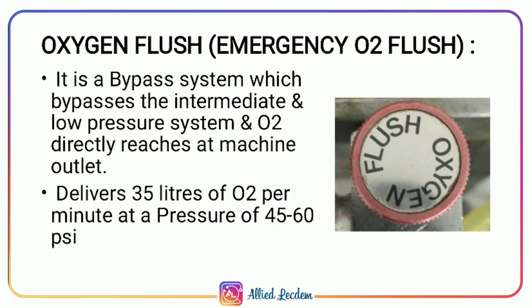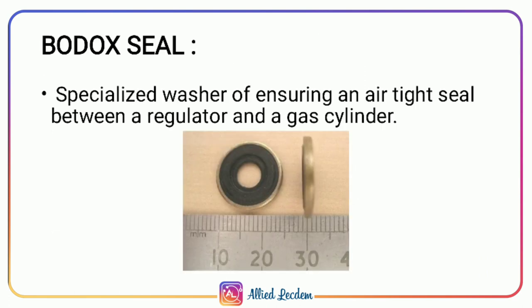The oxygen flush is an emergency bypass system which bypasses the intermediate and low pressure systems so that oxygen directly reaches the machine outlet. It delivers 35 liters of oxygen per minute at a pressure of 45 to 60 psi. The Bodok seal is a specialized washer or gasket-type structure — a rubber ring that ensures an airtight seal between a regulator and the gas cylinder.